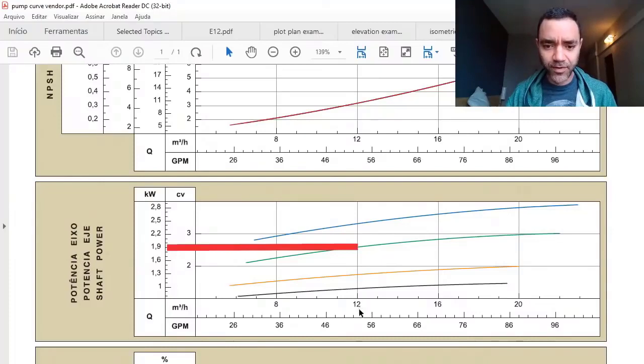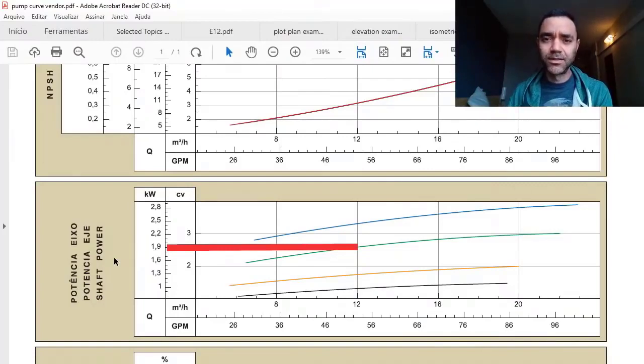You have the shaft power also related to the curve. If my pump runs at 12 cubic meters per hour using this pump, my shaft power is 1.9 kilowatts. The shaft power is not the motor size—the motor's nominal size needs to be higher or equal to the maximum shaft power of your system. When we're talking about big projects, we never use the same shaft power as the motor size when we need to comply with API or something like that; you have specific margins to be considered or complied with.